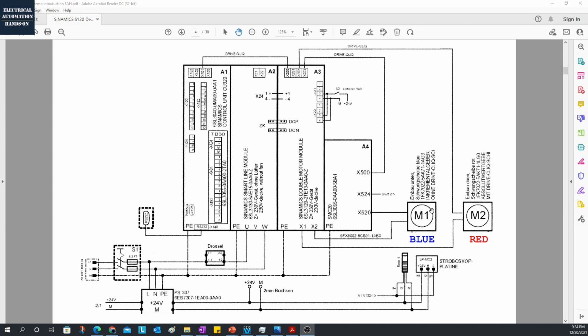On the contrary, the blue motor does not communicate directly with the servo drive. It goes to the SMC module first and then to the servo drive. That's because this blue servo motor doesn't have DRIVE-CLiQ communication. There is one interface module named SMC20, and SMC20 will connect to the motor module. That's why the CU can use DRIVE-CLiQ to identify the encoder from this right motor, but the encoder from this blue motor we have to configure manually. So it has one interface module serving this blue servo motor. That's why we need to configure this blue motor.